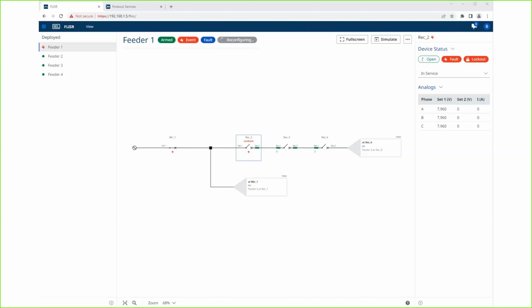And this is a little slower looking because now we're using real DNP. We have to wait for the DNP poll interval to bring us that recloser 6 status. We're waiting for it here. So you can see it's just sitting there patiently reconfiguring, waiting for recloser 6 to close. Okay, so that is deployment. We're running a little bit short on time here.